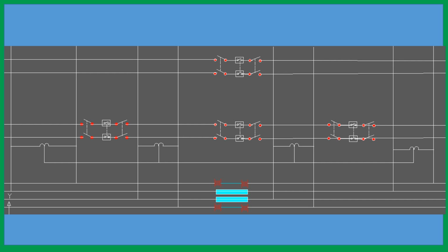The first interrupter is for paralleling for another sector, and across the neutral section there will be separate feed of two TSS. Here in the feeder wire you provide 2 cut-in insulators and the mid portion will be neutral. And in the contact catenary wire you need to provide a neutral section.